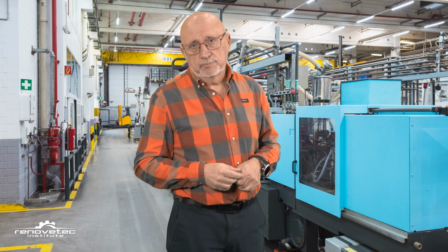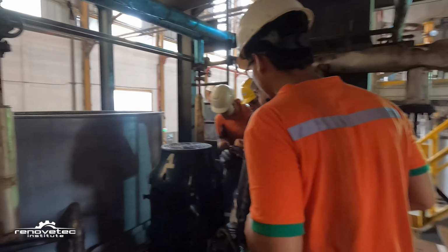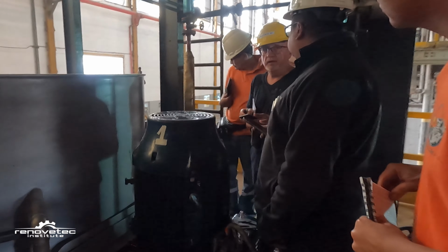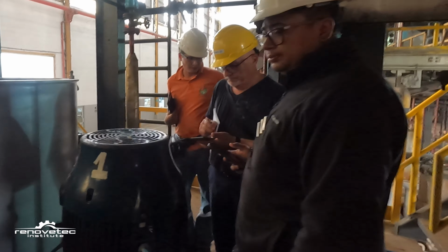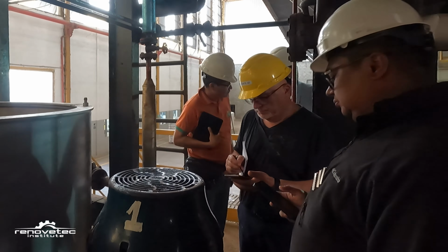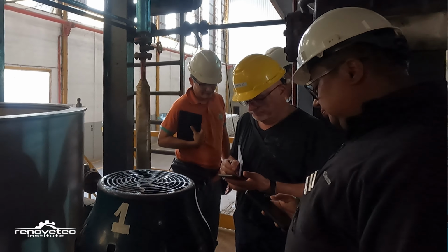Then you elaborate, first of all, the hierarchical tree of your assets, and then one by one you classify them by type and apply the corresponding protocol. After that, when you have all the tasks, you need to group the tasks into assemblies, and you prepare the different job plans of your installation. Remember, according to the item, according to the specialty, and according to the periodicity.